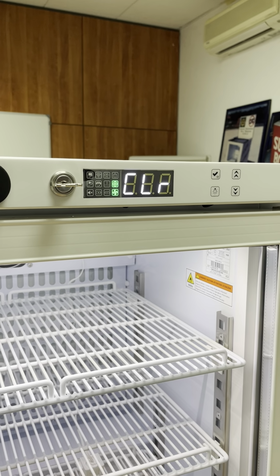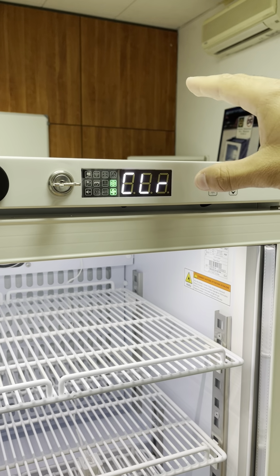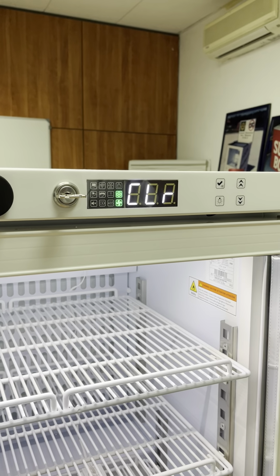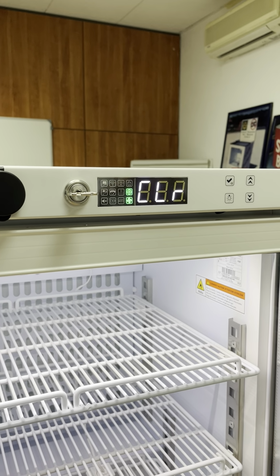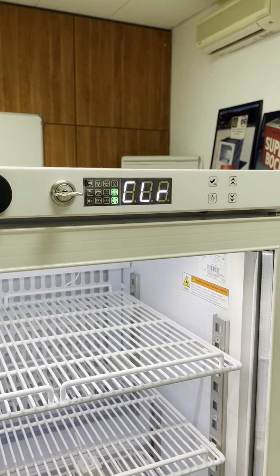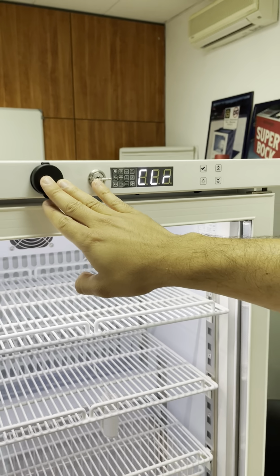So you arrive in the morning in the pharmacy, the equipment told you that there was an alarm, you go and see the max and minimum temperature. You notice, okay, there was exactly a high temperature alarm. I need to go and check on the data logger.